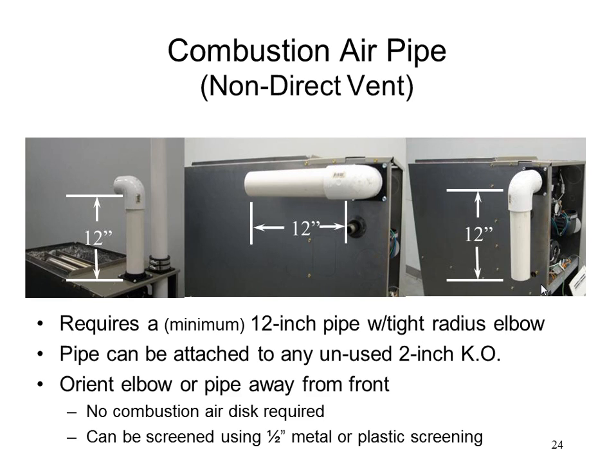So it's going to suck air in either through the cracks of your windows and doors and things like that, or what often happens is there's a naturally drafted water heater sitting next to our furnace, and that guy's exhaust pipe ends up becoming my intake for my furnace. And the fan of this furnace will overpower that, and it will negatively draw air down that flue for that water heater. So you're much better off doing a two-pipe installation in all the scenarios that you can. If for some reason you have to do a single pipe, this furnace can be used that way. You just got to think about how you're going to get your combustion air into the room. But when you do the single pipe installation, you do have to put a little bit of pipe on the inlet side of the furnace. You got to see a little bit of restriction on that fan motor in order to be able to generate some decent static. So you got to put basically a 1-foot pipe and an elbow on there. Doesn't matter which direction you point it. Get an elbow and a foot of pipe on there to get a little bit of restriction.